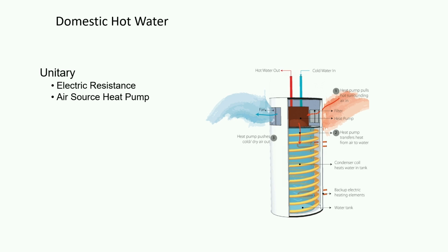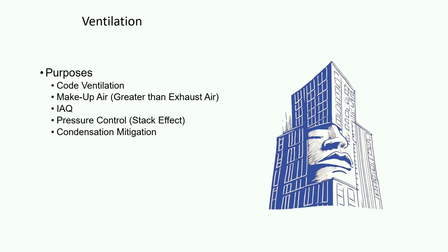Sometimes they do unitary hot water, not generally on larger buildings, but sometimes they do, which certainly could be the case. Most of the time that's going to be electric. If you have heat pumps in the suite, depending on the style of heat pump, maybe you could do some type of a hot water assist off of the heat pump system. If it's a vertical stack, probably not. But if it's an actual packaged water to air heat pump, there's a possibility there. So it just depends.